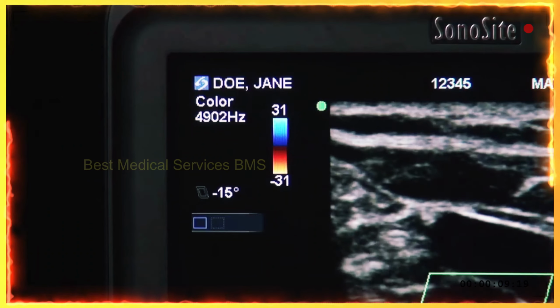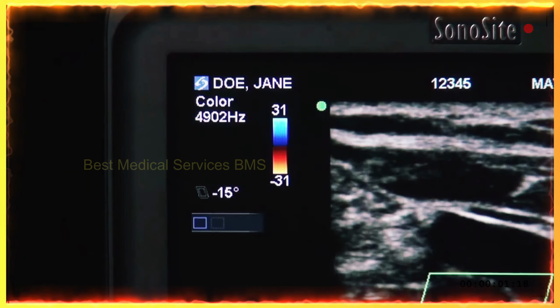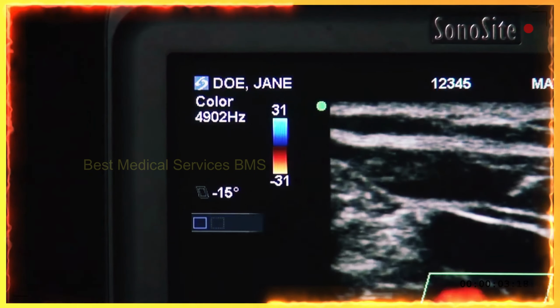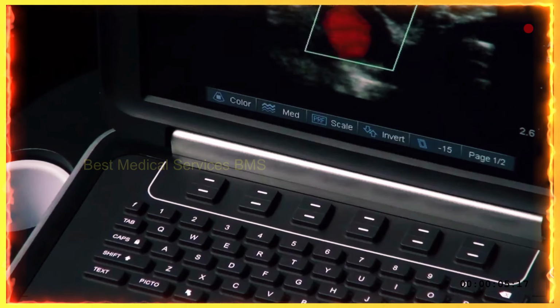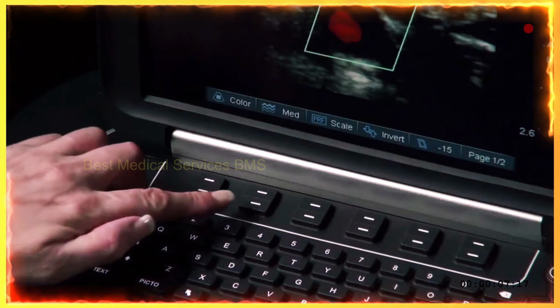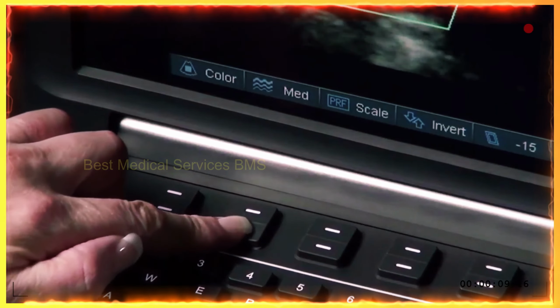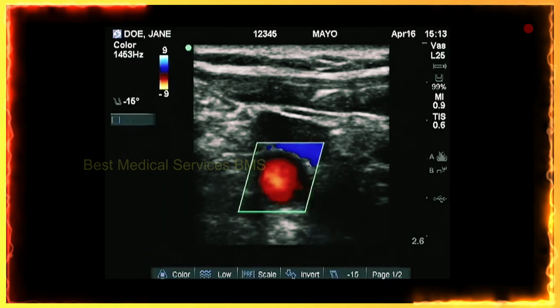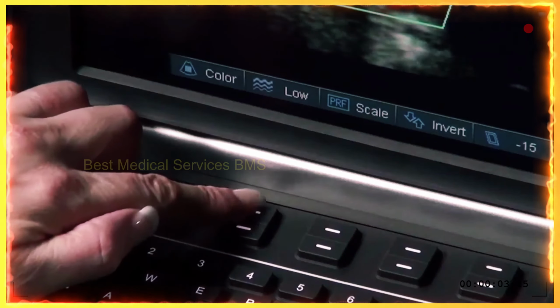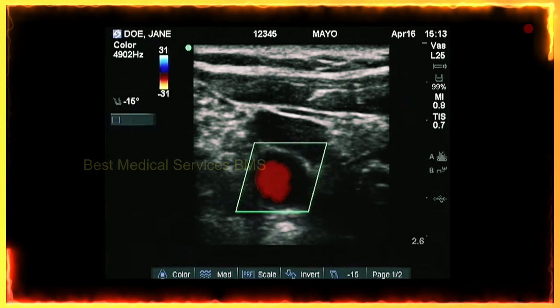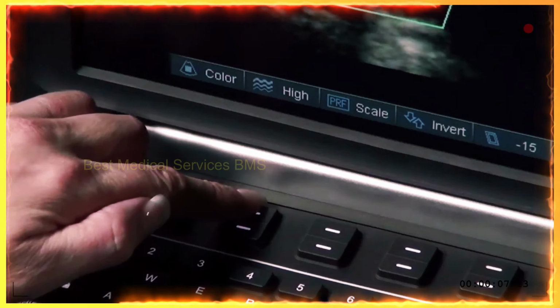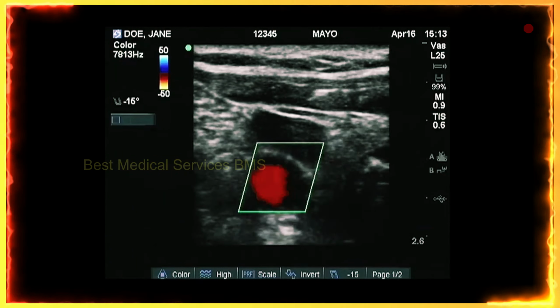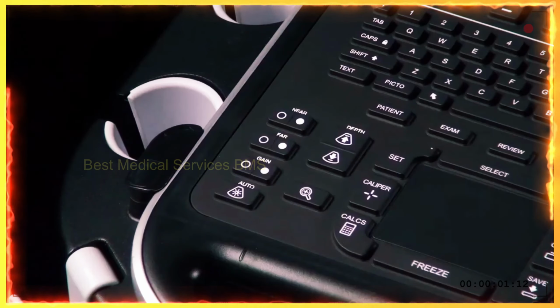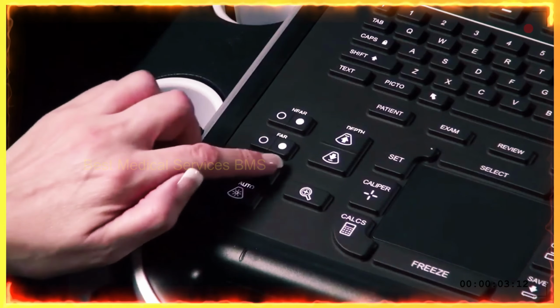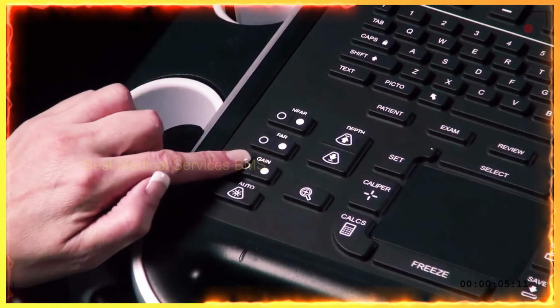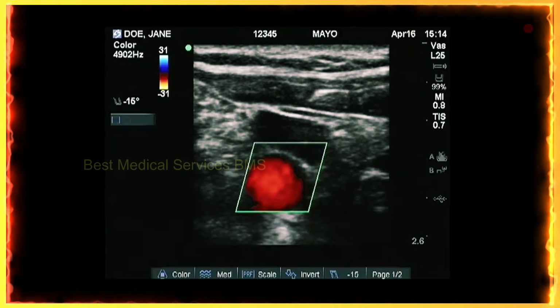The settings for color will be displayed in the top left corner of the screen. Select the desired sensitivity from the on-screen context menu. Low optimizes the system for low flow state. MED optimizes the system for medium flow states. High optimizes the system for high flow states. Use the Gain key to adjust the overall color gain level for Color Power Doppler or Color Doppler.